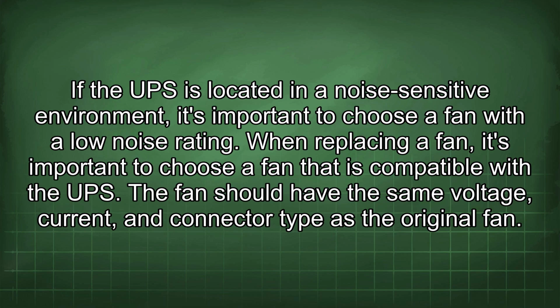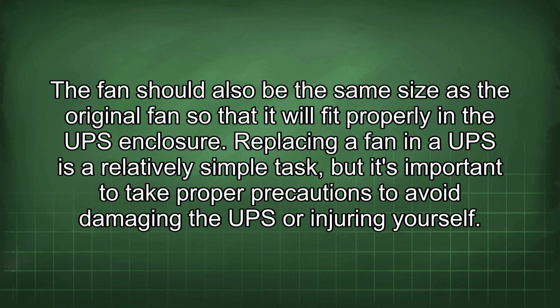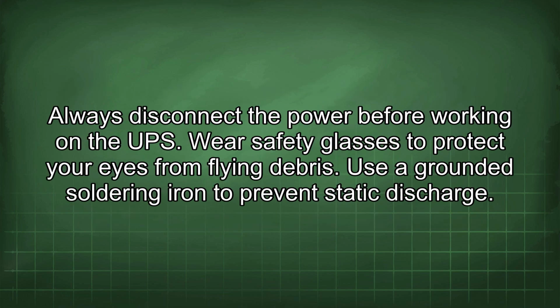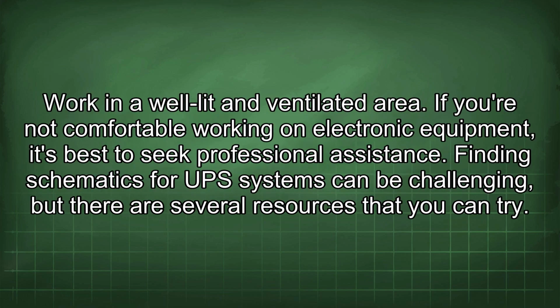When replacing a fan, it's important to choose a fan that is compatible with the UPS. The fan should have the same voltage, current, and connector type as the original fan. The fan should also be the same size as the original fan so that it will fit properly in the UPS enclosure. Replacing a fan in a UPS is a relatively simple task, but it's important to take proper precautions to avoid damaging the UPS or injuring yourself. Always disconnect the power before working on the UPS. Wear safety glasses to protect your eyes from flying debris. Use a grounded soldering iron to prevent static discharge. Work in a well-lit and ventilated area. If you're not comfortable working on electronic equipment, it's best to seek professional assistance.